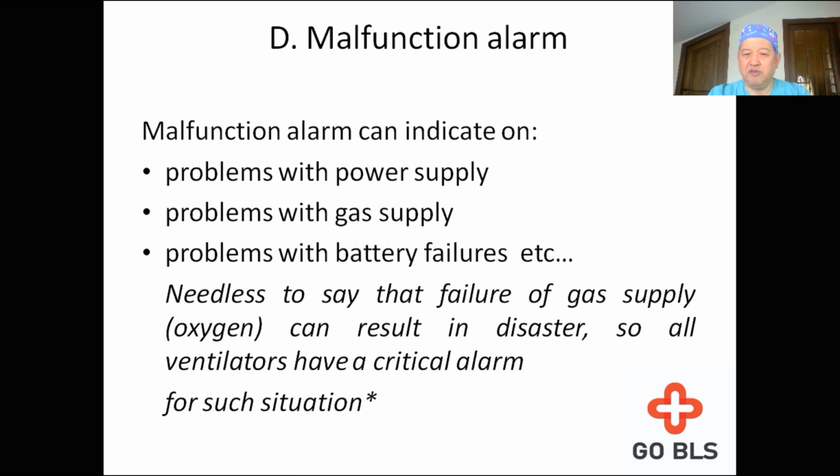Needless to say that failure of gas supply, especially oxygen, can result in disaster. It can result in the death of the patient. So all ventilators have a critical alarm for such situation.